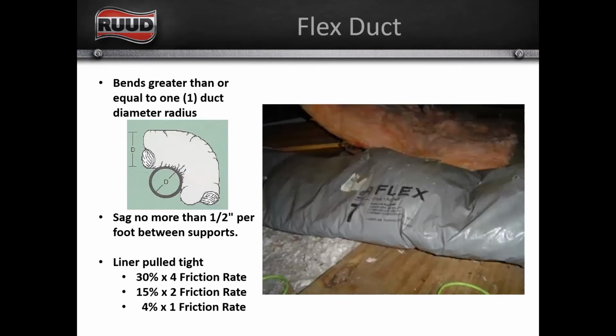So I mentioned flex duct a couple of times, and I don't want anybody to misconstrue what I'm saying. I'm not suggesting that we don't run flex. I'm saying if we're gonna run flex, which we are, right, that we run it correctly. And correctly means, you can see in this photo that this piece of flex is just completely smashed and destroyed. It says this is a 7. There's no way this is a 7-inch round anymore. I don't know what that size would be equivalent to, but it's not a 7.